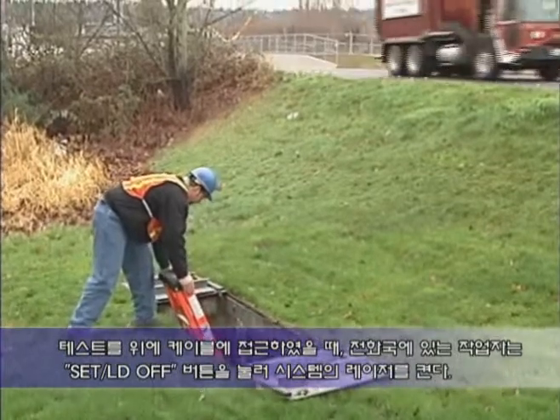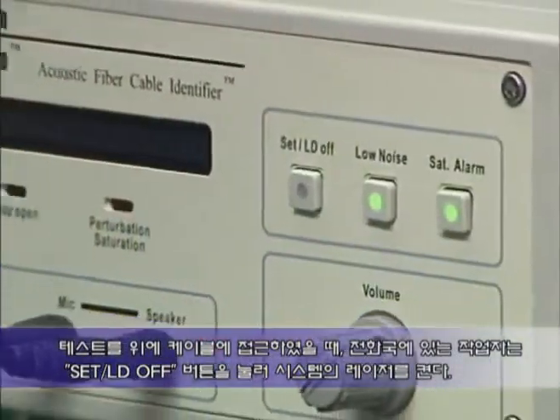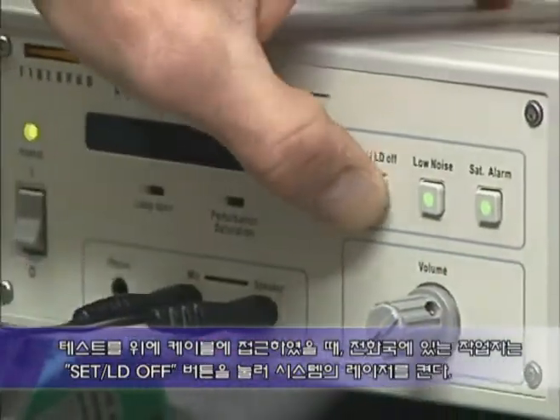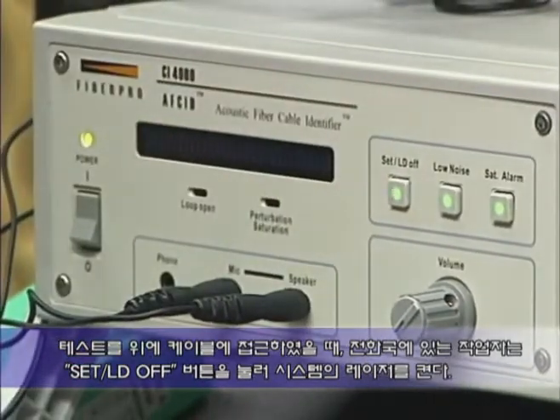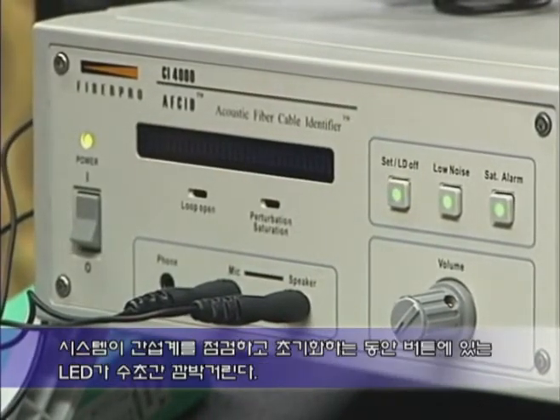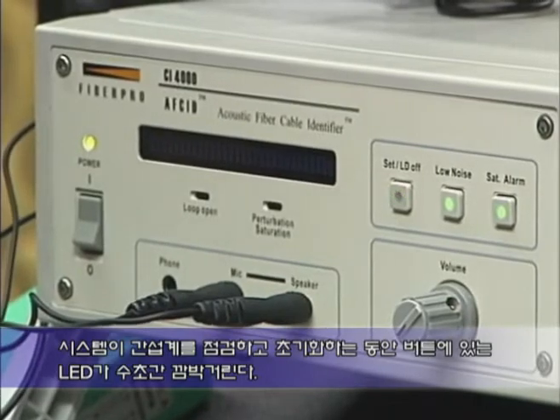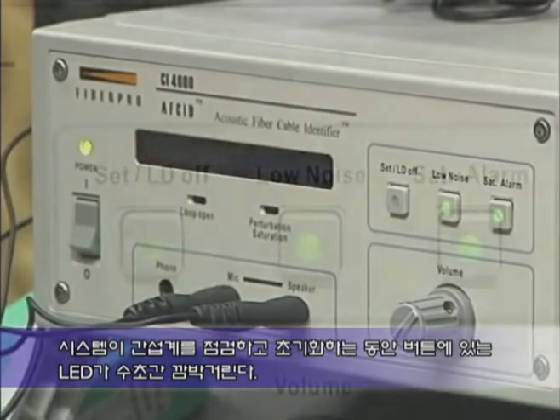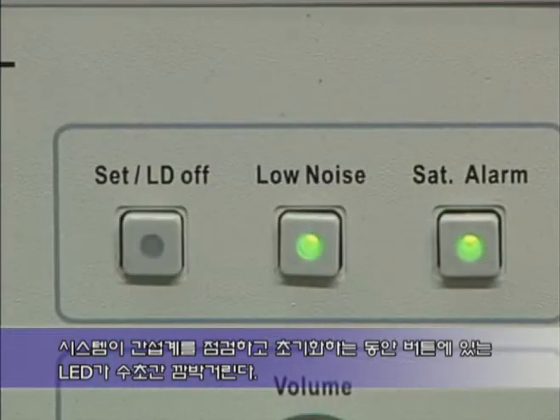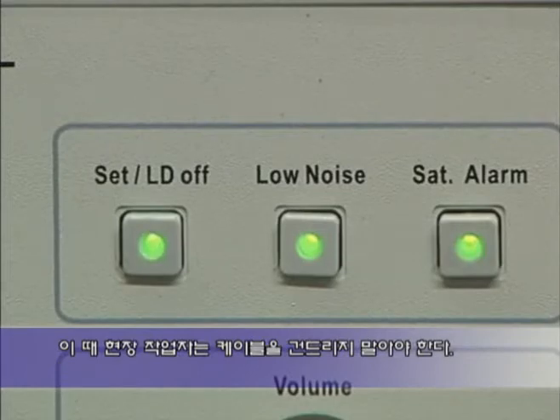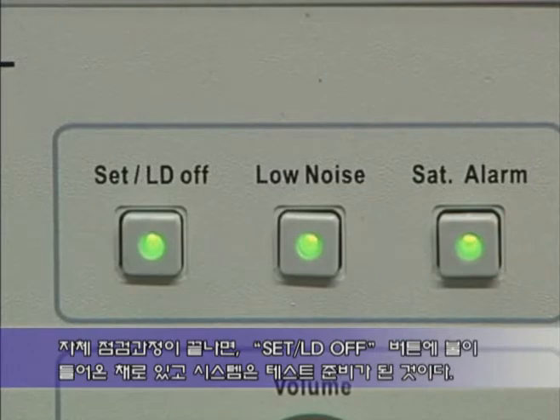When the cables have been accessed for testing, the central office technician presses the Set LD Off button to start the instrument's laser. The LED and the push button will flash for a few seconds while the instrument calibrates and initializes the interferometer. During this time, the field technician must not disturb the cables. When the calibration is complete, the Set LD Off button will remain illuminated and the instrument is ready for testing.